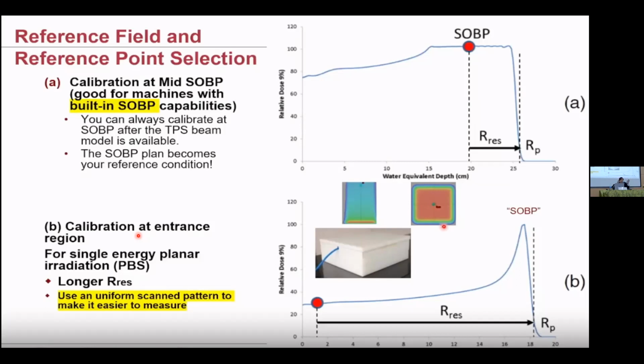So you could do it two different ways, doing absolute calibration. Most do it this way. In your treatment planning system, you're probably going to have to do these measurements because in this measurement, this is really how you're going to end up changing the number of protons to a monitor unit value. So you're actually going to be counting protons when you do it this way. Again, there's no clear regulation or recipe exactly to follow.